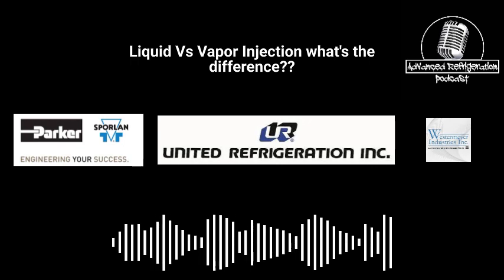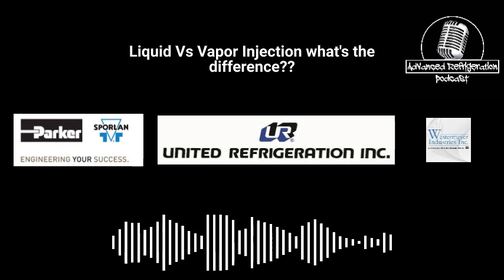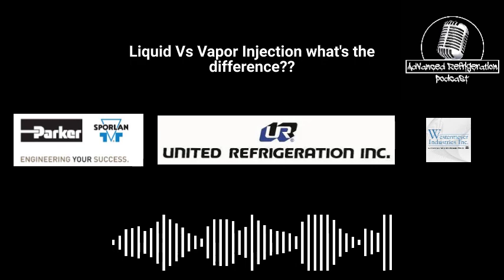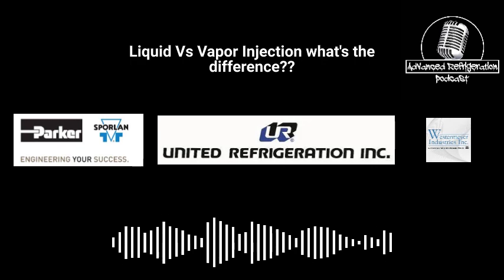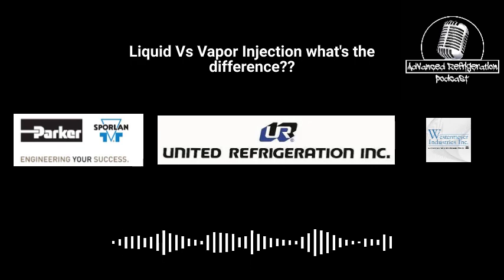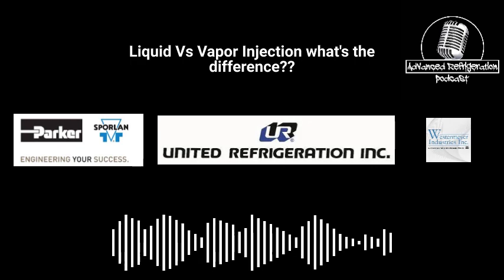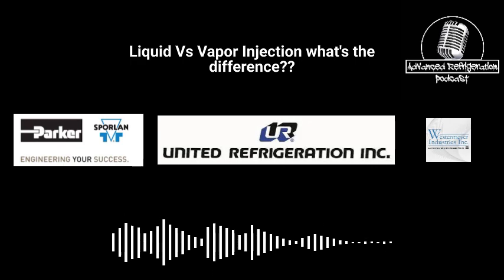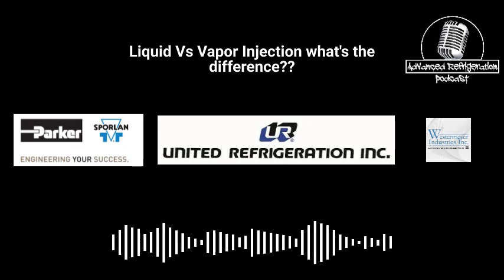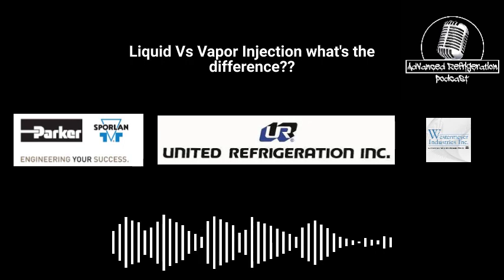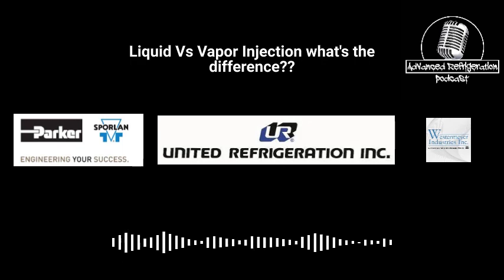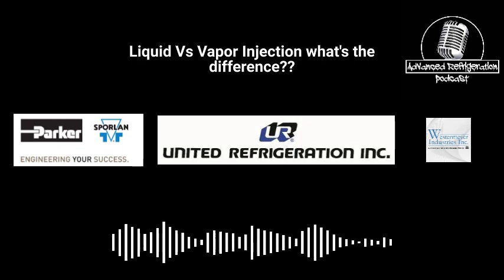It's going to allow your liquid temperatures to be a lot more stable. You're going to have more subcooling, better quality liquid. You're going to get more net refrigeration effect out of your evaporators. So that's where it becomes more efficient, because now you have that subcooler, but you didn't pay for it. The other thing is the vapor injection also does increase the efficiency of a system up to like 20%. So you could potentially get 20% more BTUs out of a compressor when you're utilizing that vapor injection.